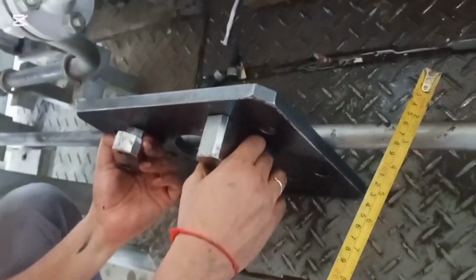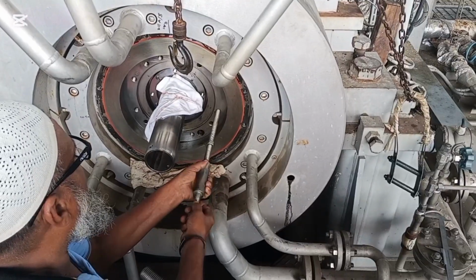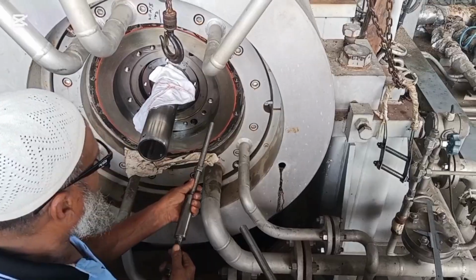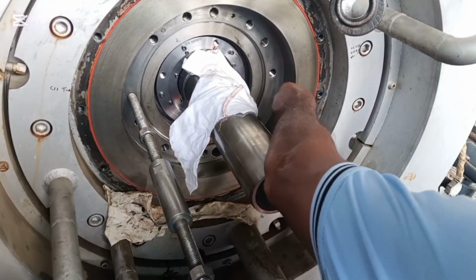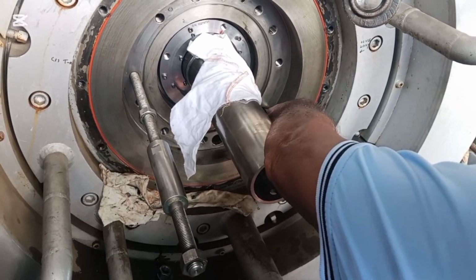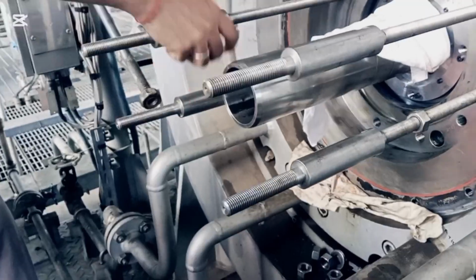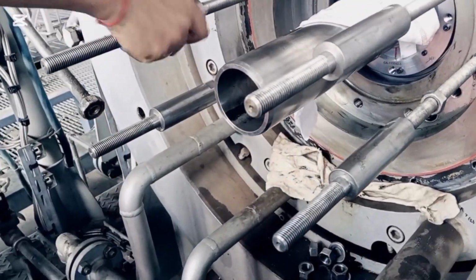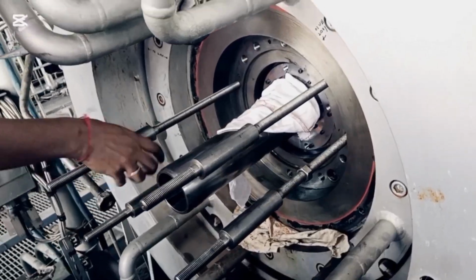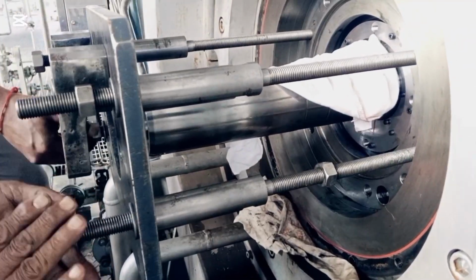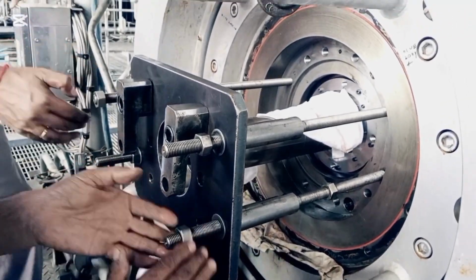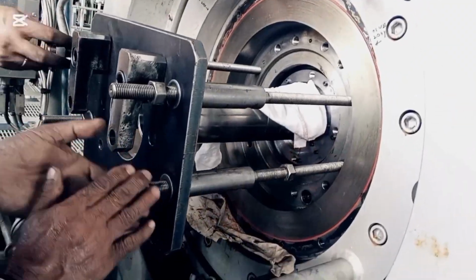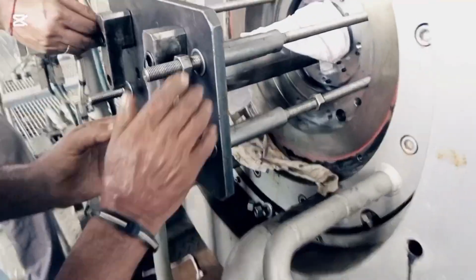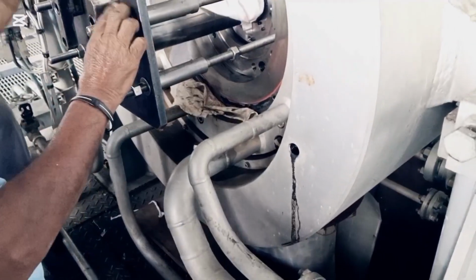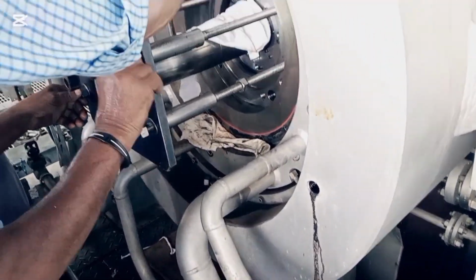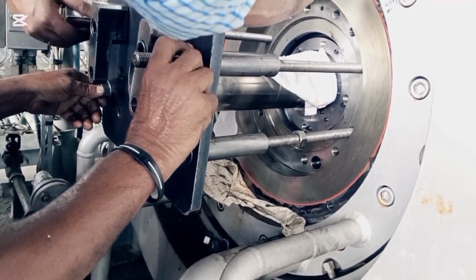Here is also a base unit. It is needed to dismantle part of the seal unit, and here are some special bolts, and after connecting the bolts the base is placed over the bolts, and when we tighten the middle bolt then the upper part is opened from its base. The disassembly procedure is likely the reverse of the assembly procedure, so always we need to measure different clearances for proper maintenance work.